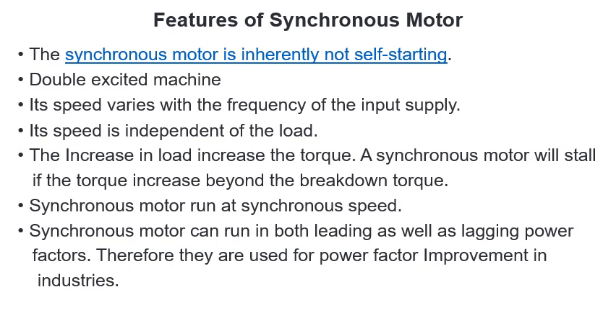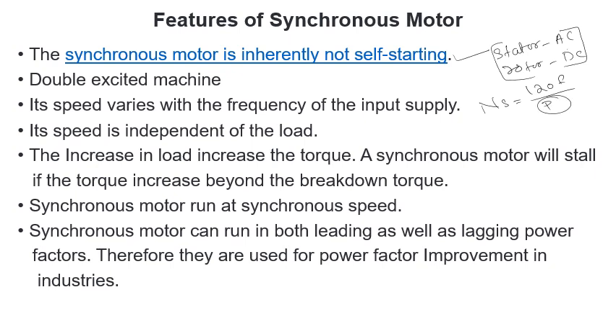Here you can see some features associated with synchronous motors. First, it is not self-starting — we have already seen the reason. Second, it is a double excited machine: the stator needs AC excitation and the rotor side needs DC excitation, and both excitations are necessary for proper working. Third, the speed can be varied only by changing the frequency, because synchronous speed NS equals 120f divided by P and the number of poles is fixed — so the only way to change synchronous speed is by changing the frequency.